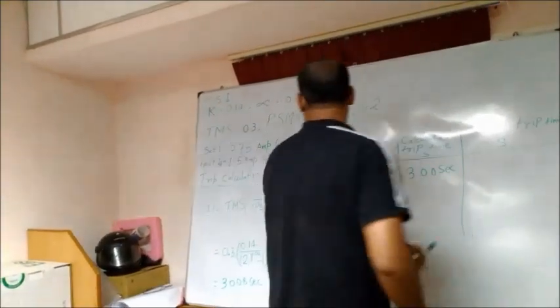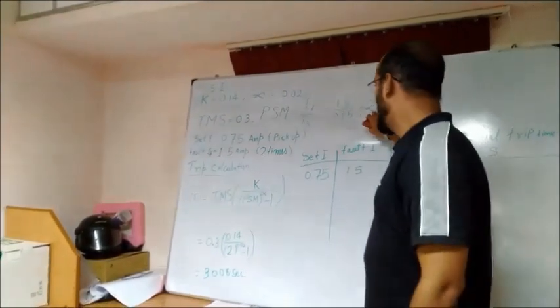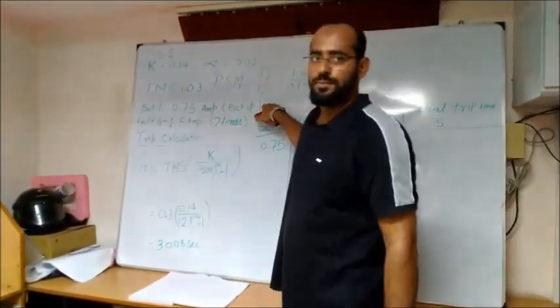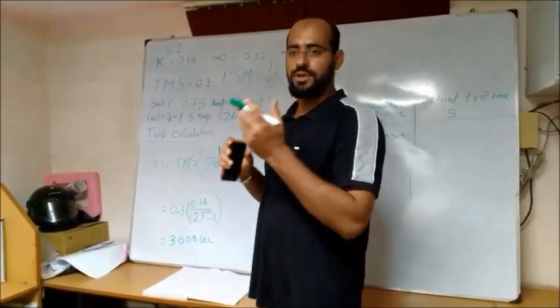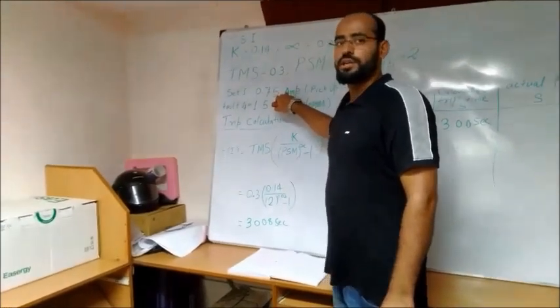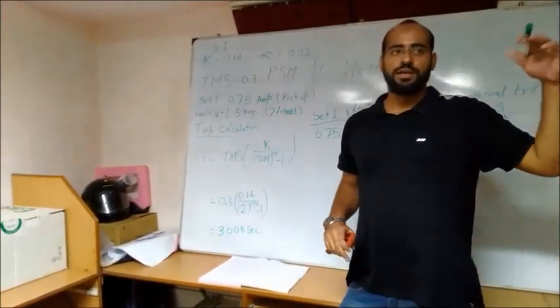And PSM is our fault set current divided by our set current. That is already calculated in 2. PSM is 2. And the set current is 0.75 ampere. I set here. Already I set in 0.75. So that is our pickup current means when the disk is start rotating but not fully rotated but start rotated. That is our pickup current. So and we inject here 2 times of set current.